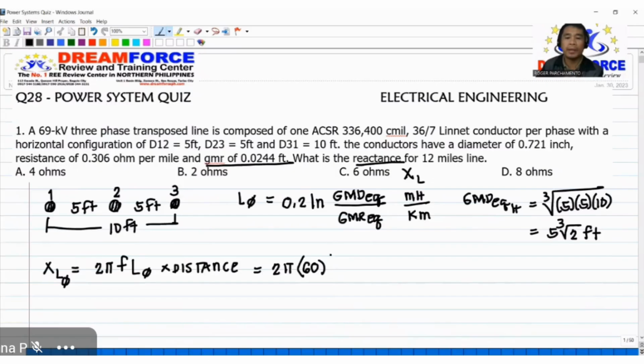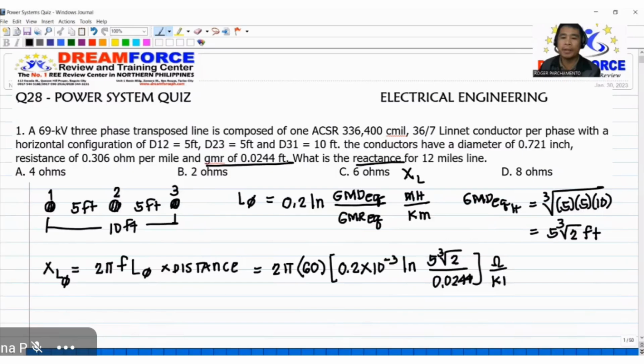So multiplied by L, that is 0.2. So milli there, so that is 1 times 10 to the negative 3. So the unit will become ohm per kilometer. Times ln of GMD equivalent is 5 times cube root of 2, then divided by 0.0244. The resulting unit of this is ohm per kilometer. So multiplied by 12 miles, then times 1.609 kilometers in 1 mile. So kilometers will be cancelled.